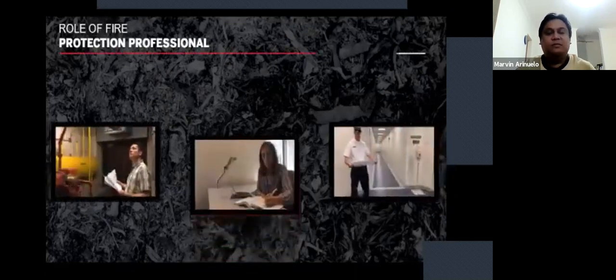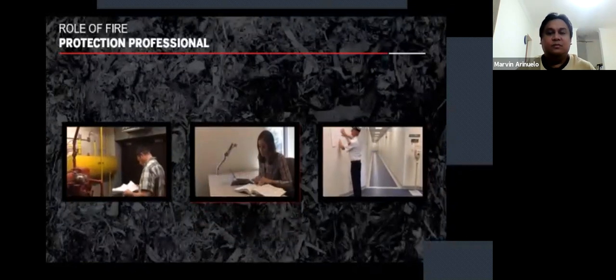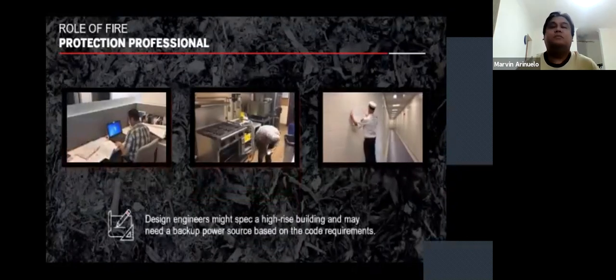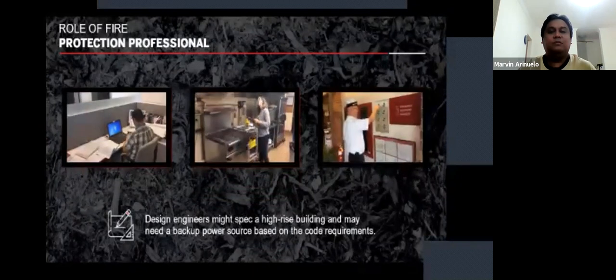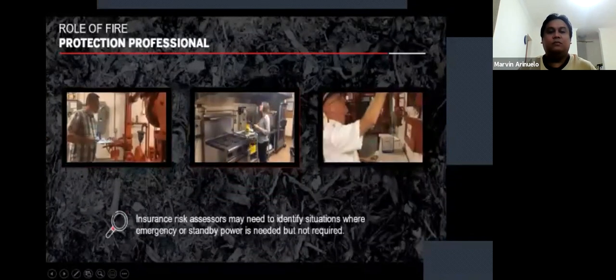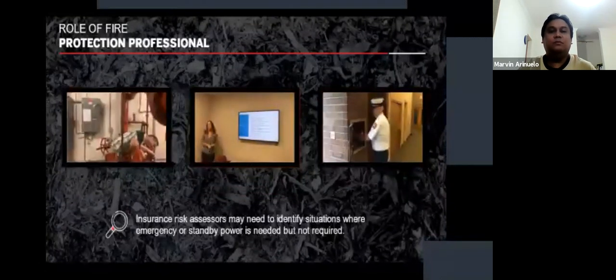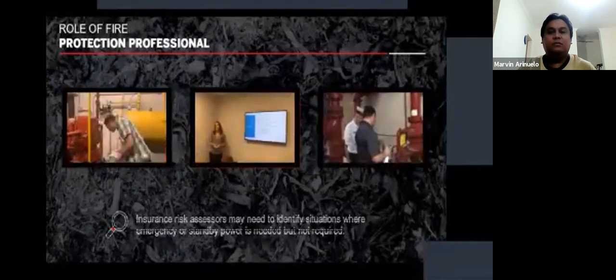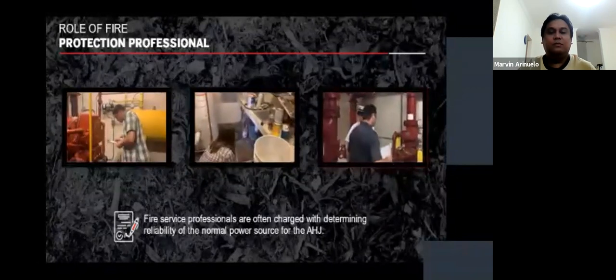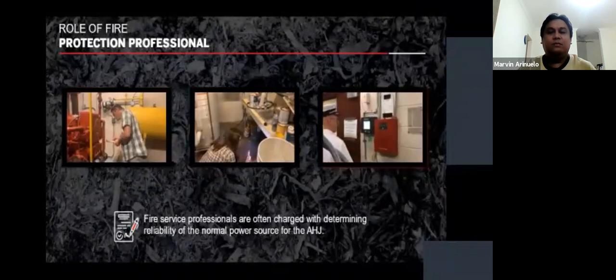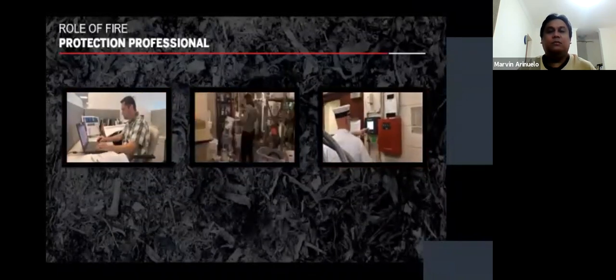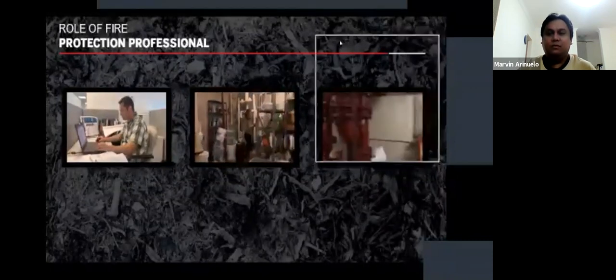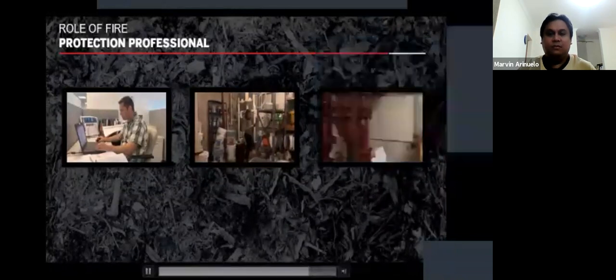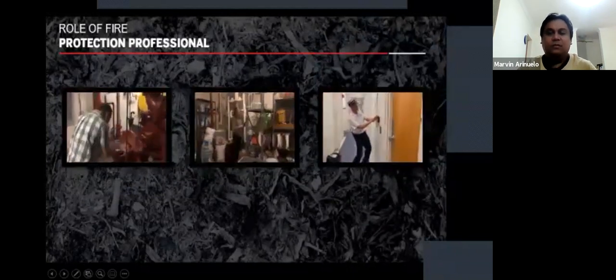So let us determine the role of the fire protection professional. As a fire protection professional, you also need to consider other aspects related to standby and emergency power. Design engineers might spec a high-rise building and may need a backup power source based on the code requirements. Insurance risk assessors may need to identify situations where there is a value to the building or business that may require emergency or standby power where the code does not require such a system. Fire service professionals are often charged with determining the reliability of the normal power source for the authority having jurisdiction, or AHJ. Fire service would obtain data from the normal power provider about the number of times power has failed, whether there are power lines above or below ground, and whether these connections are subject to natural disasters.